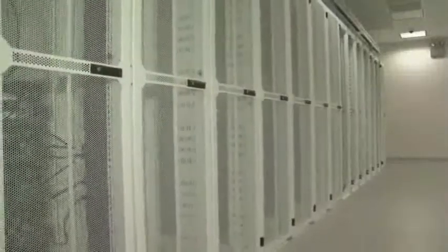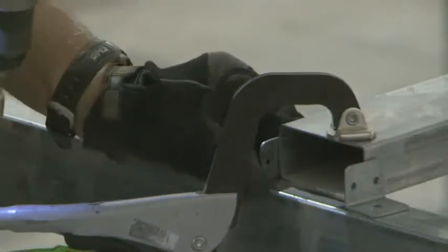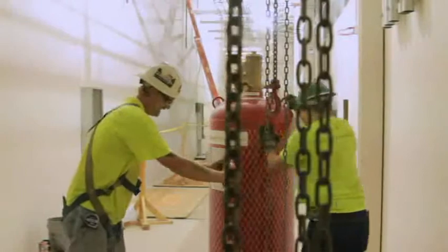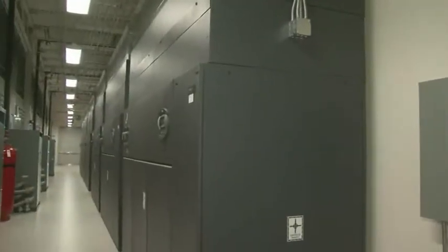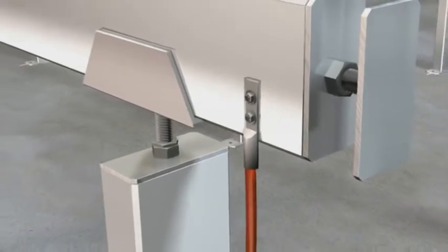The panel system itself is a very strong flooring system. Because of the substructure being a tube steel frame, it is much more weight bearing than a traditional pedestal floor. So it did not require us buying extra support materials that go underneath the floor to support heavier equipment, whether it be the cooling loads, the PDUs, or actually the heavy cans that are out there. We're able to put them directly onto the floor. We're able to actually utilize less grounding points as well, where we only needed 2 in the space.